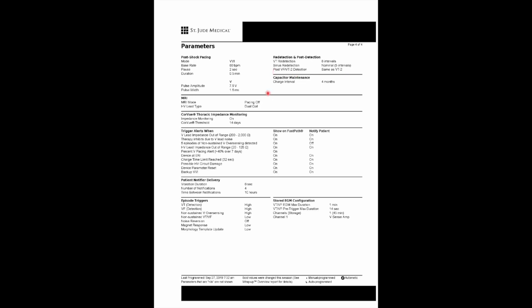This is our capacitor maintenance, so the charge interval is going to be every 4 months. It's going to test itself. MRI mode, pacing is going to be off, and then it's asking what type of high voltage lead it is. In this case, it's a dual coil lead, meaning it has a coil in the SVC as well as one in the RV. And then we can see our CorVue monitoring is turned on and the threshold is 14 days. So it has to have an impedance range under the reference range for 14 days in order to call it a status alert. These are more triggers.